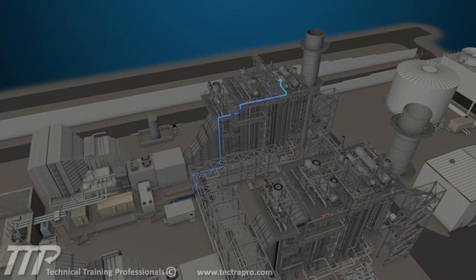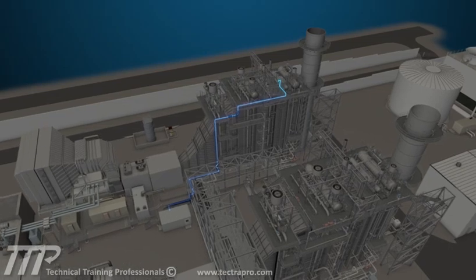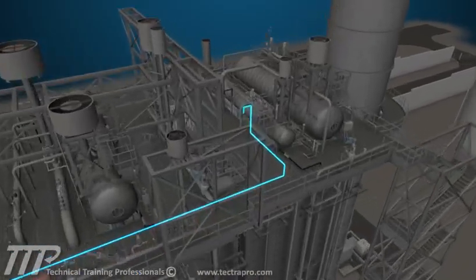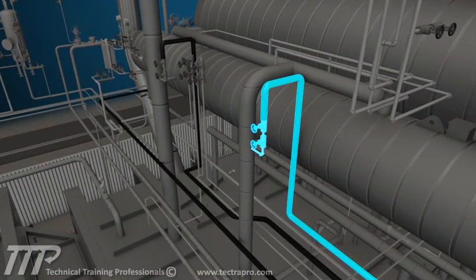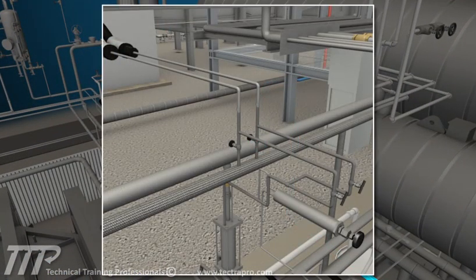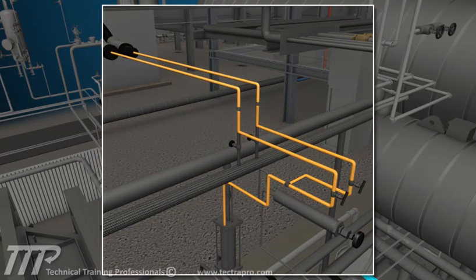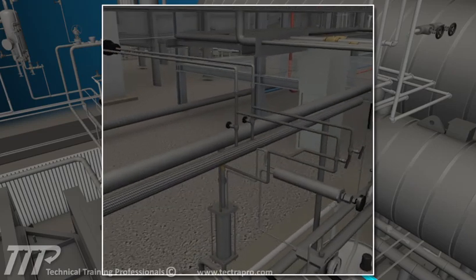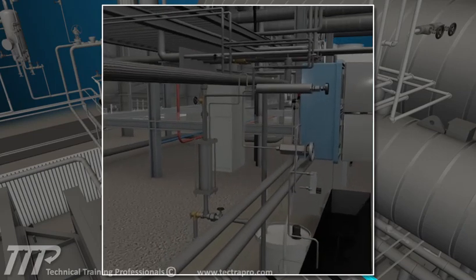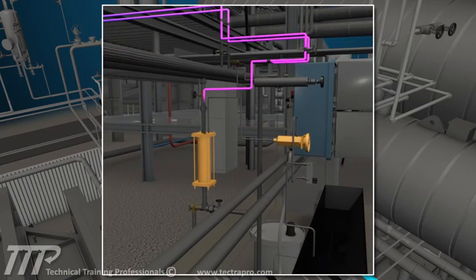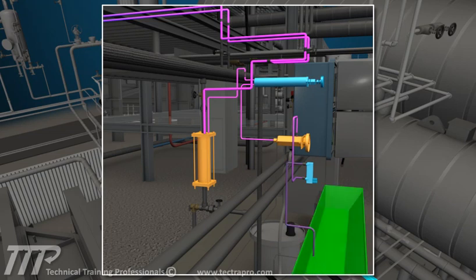Samples 9 and 10 are the intermediate pressure drum steam 1 and 2 upstream of the IP superheaters. Both samples utilize the same sample panel components. The operator must manually line up the intermediate pressure drum that is to be sampled. At the sample panel, this sample point only provides a temperature reading and flow adjustment. The water is then directed to a trough, where an operator can obtain a grab sample.